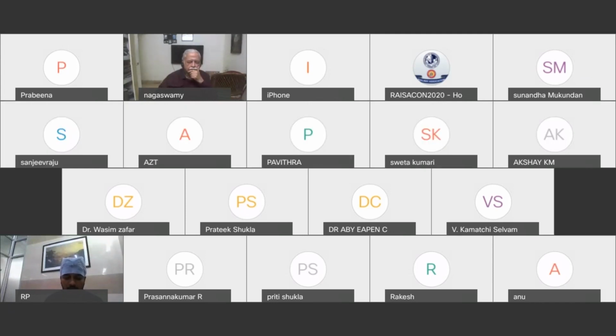Before the flow control valves, the pipelines consist of non-interchangeable quick couplers, the DISS diameter, and accessible pipelines which are color coded. The cylinders are color coded and have the pin index safety system, and the master switch, which when turned on, turns on all the alarms. And the pressure regulators, and oxygen pressure failure safety devices. At the flow control valve, oxygen ratio control devices.